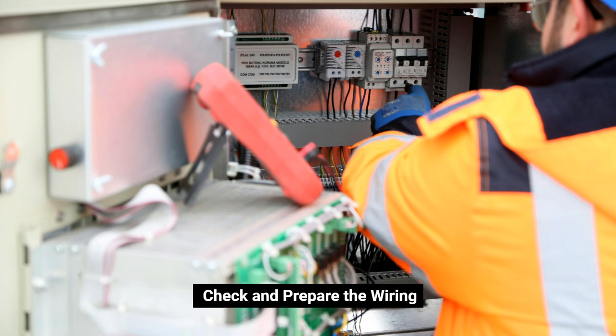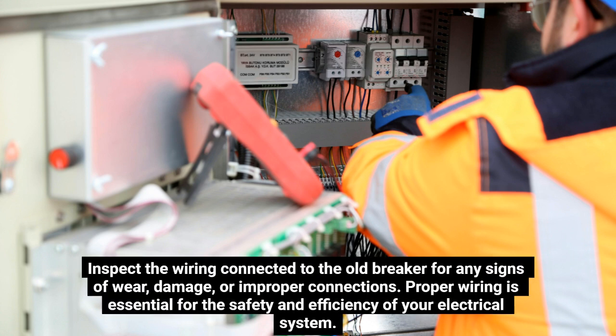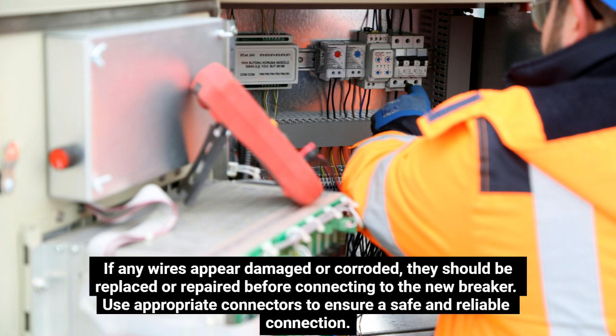Check and prepare the wiring. Inspect the wiring connected to the old breaker for any signs of wear, damage, or improper connections. Proper wiring is essential for the safety and efficiency of your electrical system. If any wires appear damaged or corroded, they should be replaced or repaired before connecting to the new breaker. Use appropriate connectors to ensure a safe and reliable connection.